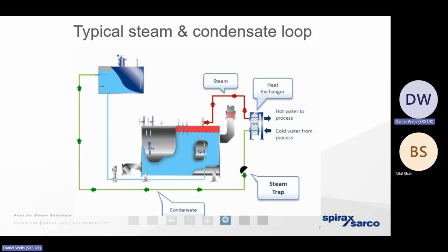Because if we don't, that condensate is going to back up, it's going to flood the heat exchanger. We've got a barrier to heat exchange, or it can flood the distribution pipework as well. And that's why we drain the condensate away from the bottom of the heat exchanger. Steam coming in at the top, and the pressure within the steam heat exchanger is also helping to push the condensate away. So the pipe in green, that's much smaller than the connecting steam pipe, because we know condensate is a single phase, non-compressible liquid. So we get that condensate out of the heat exchanger as quickly as we can.